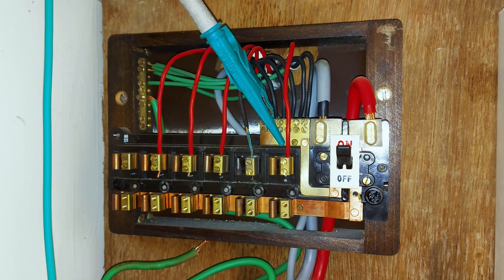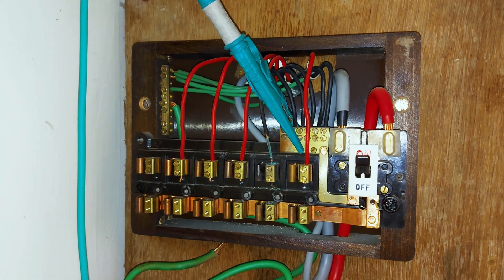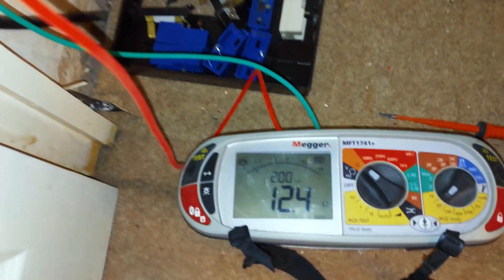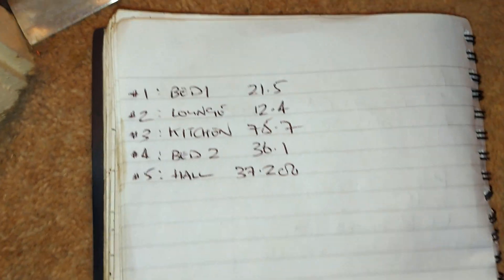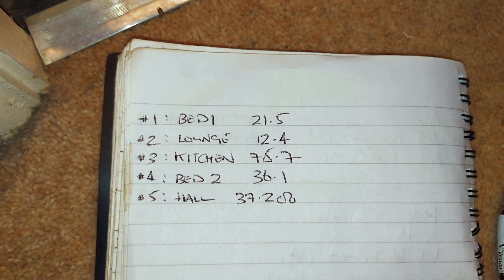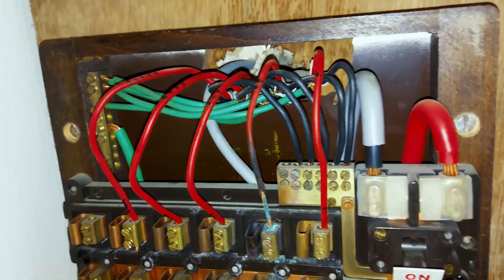Now we're just going to repeat that process on every single fuse until we identify the remaining three circuits. We're just testing the circuit with some thermal damage there, and that circuit is giving us a reading of 12.4 ohms — I've already put that in the book. There are all the readings for all the circuits, and as you can see the lounge is the biggest circuit with a resistance reading of 12.4 ohms. They've all tested out reasonably well.